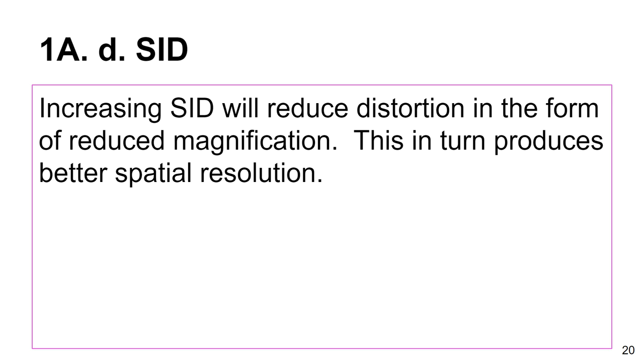In terms of SID's effect on distortion, we're talking about magnification — changing the size. When we have magnification, we get distortion, and when you have distortion your spatial resolution goes down. So higher SID is better.